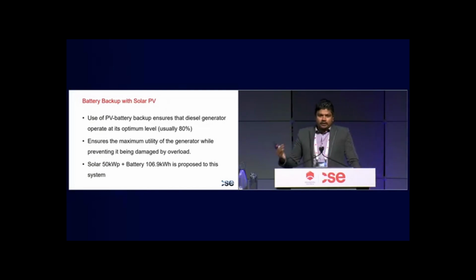But you cannot say that even though you do various things, there won't sometimes be fluctuations. Even though you come to 300, it can go to 330, 340 at different times. If that happens and you switch on another generator, the load is divided among two generators, so again the efficiency goes down. To make sure that won't happen, I'll be proposing a battery bank with some solar assistance in particular sizes.